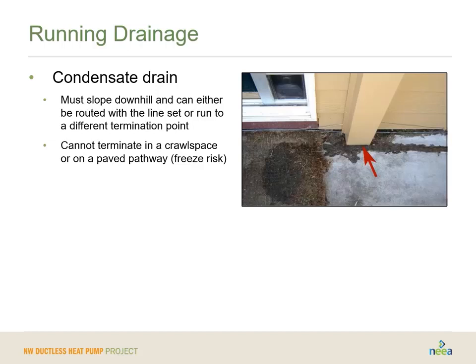The condensate drain, I mentioned this earlier. It must slope away from the building. As you can see here, if you have it sloping towards the building, you have that potential for creating little pockets of moisture that could attract rodents or creating building damage. And please do not terminate these into a crawl space or on a paved pathway. It's just problematic for a number of reasons, one of which could be even freezing risk from any condensate.